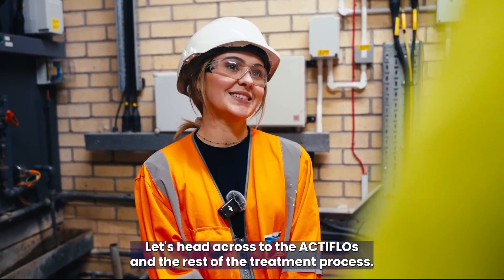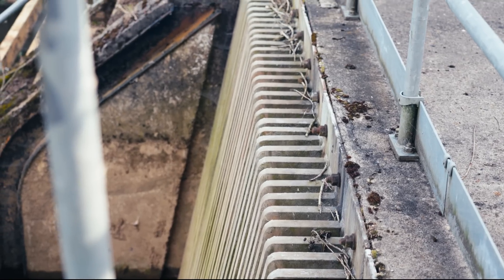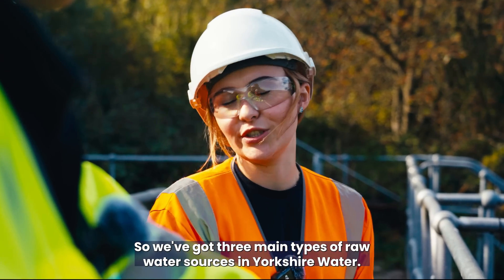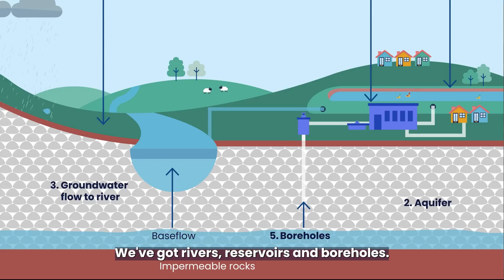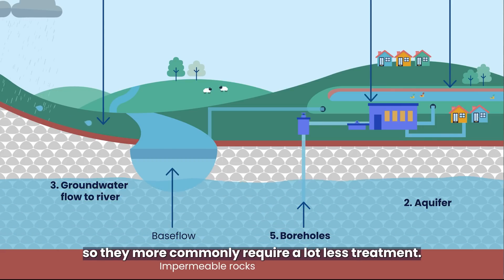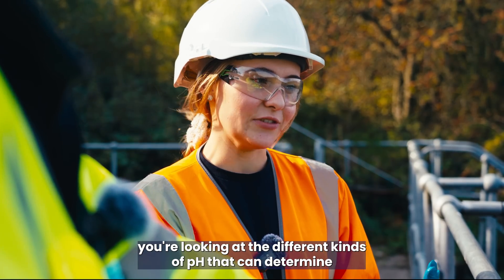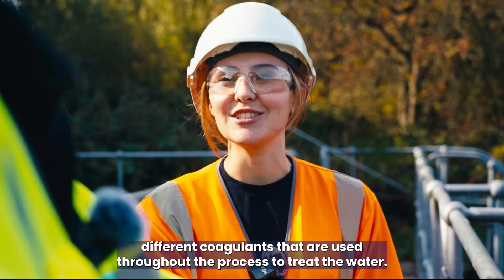Let's head across to the ACTIFLOs and the rest of the treatment process. We're here now at the river. How do different raw water sources affect the way we treat the water? We've got three main types of raw water sources in Yorkshire Water: rivers, reservoirs, and boreholes. Boreholes are groundwater and commonly require a lot less treatment, whereas rivers and reservoirs have different kinds of pH that determine different coagulants used throughout the process.